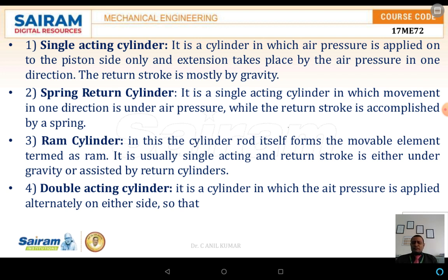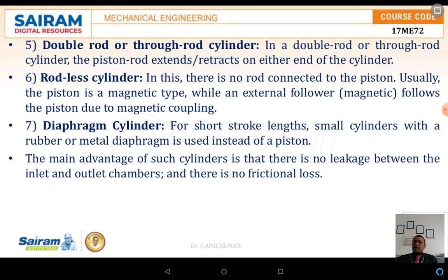The ram cylinder is a cylinder where the rod itself is the movable element, termed as a ram. It is usually single acting, and the return stroke is either under gravity or assisted by means of a return cylinder. The double acting cylinder has pressure applied on alternative sides, by which the movement of the piston is done by means of pneumatic air or hydraulic pressure. This type of cylinder has a double rod at both ends, and the piston rods extend or retract on either side of the cylinder.